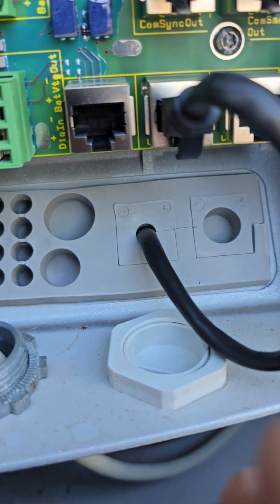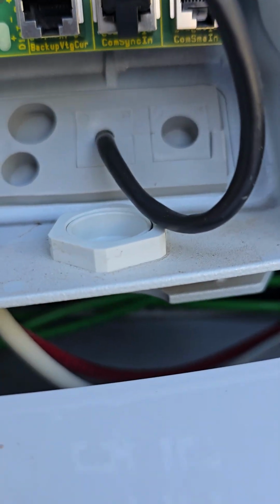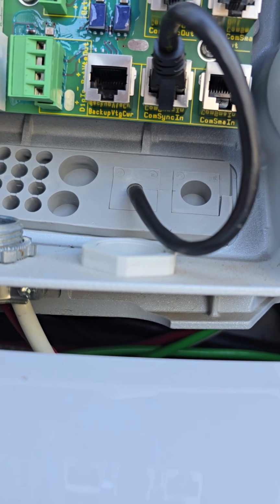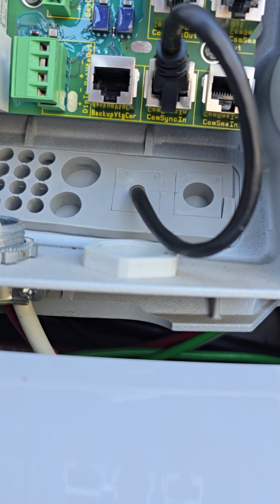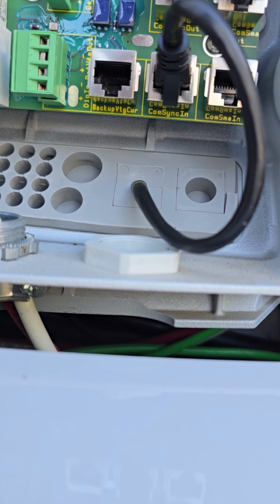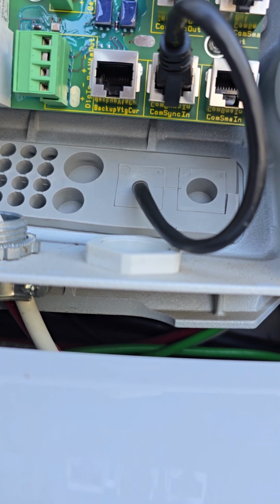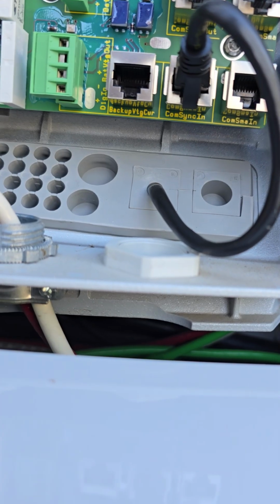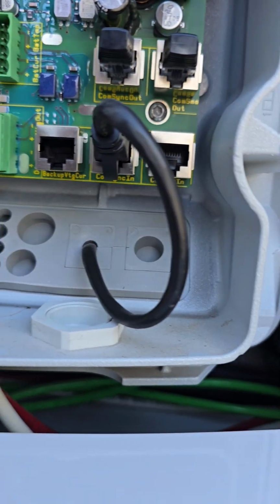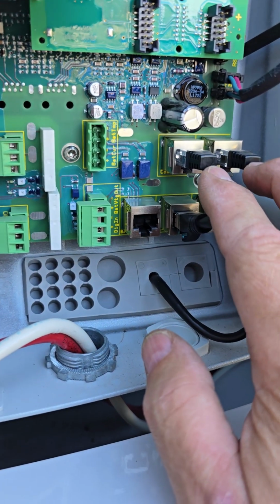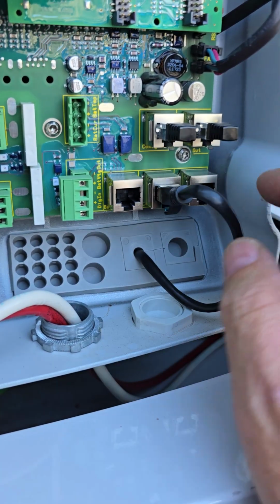Anyway, notice over here, this is the slave. Let me zoom in right there. It's so hard to get under there. You can see that it says communication sync in, right? So all the bottoms are the ins and then the tops are the outs, okay? And then the slave has the 2 terminators in here, which means there's no slave downstream of us, and the master is feeding into the slave.